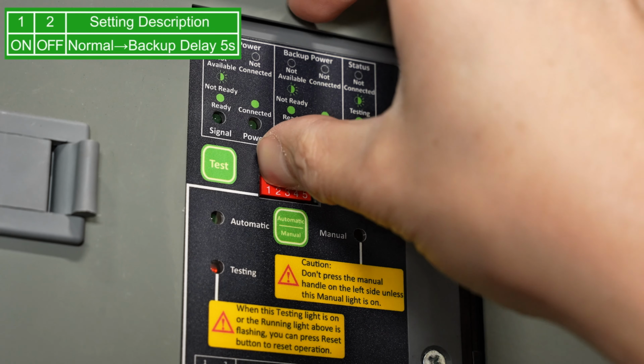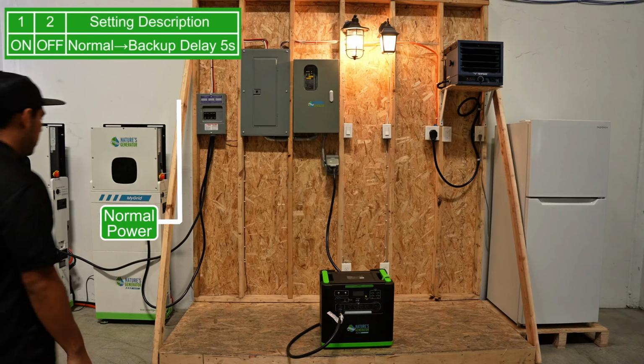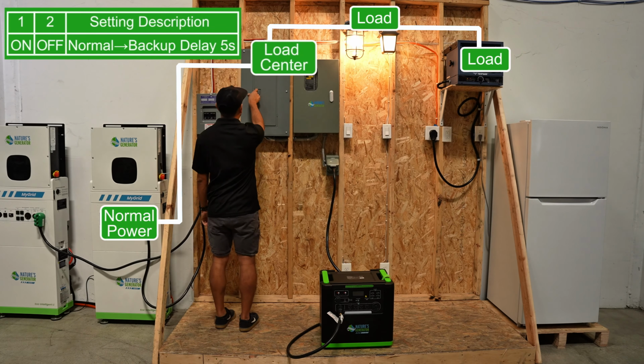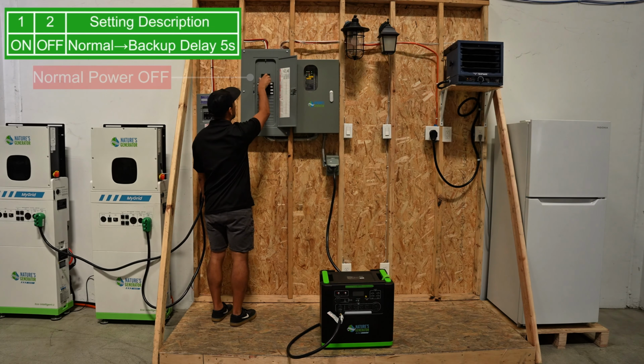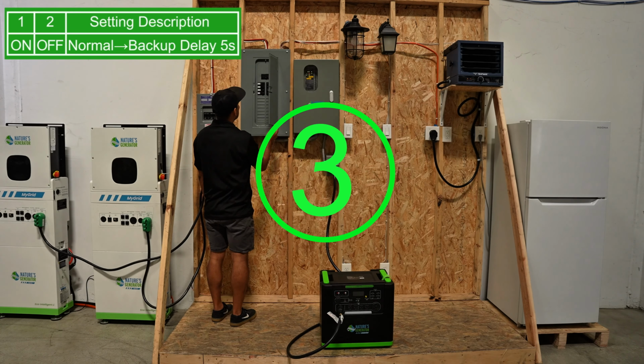Here is the setting table for the first and second switch. We use the on or off position to set the delay time before switching from the normal power to the backup power. Here, we set a 5-second delay.